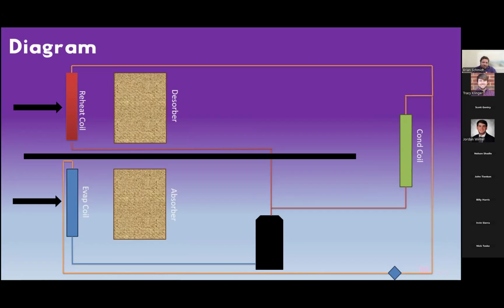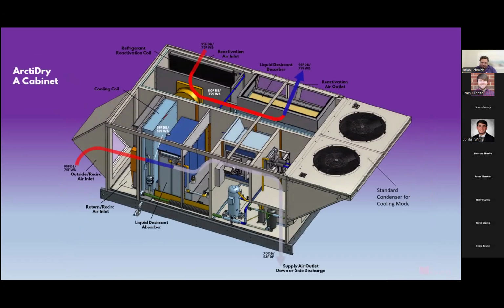It is reconcentrating it based on the heat provided by our hot gas reheat coil. So what does this look like in real life? Here's a nice diagram of our unit. As you can see, there's a wall right down the middle of the unit. These two paths do not share any air whatsoever. There's no parasitic heat transfer or anything like that, like you would have in a solid desiccant wheel.